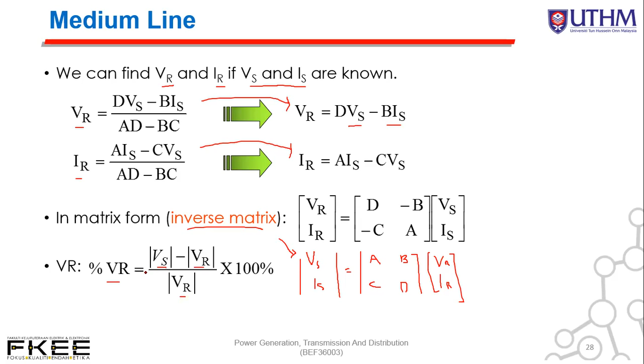Okay, look at example 6.3: a 345 kilovolt, three-phase transmission line, 130 kilometers long. Resistance per phase is 0.036 ohm per kilometer. Inductance per phase is 0.8 millihenry per kilometer. Shunt capacitance is 0.0112 microfarad per kilometer.